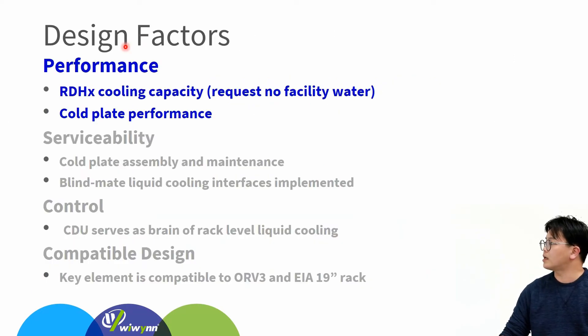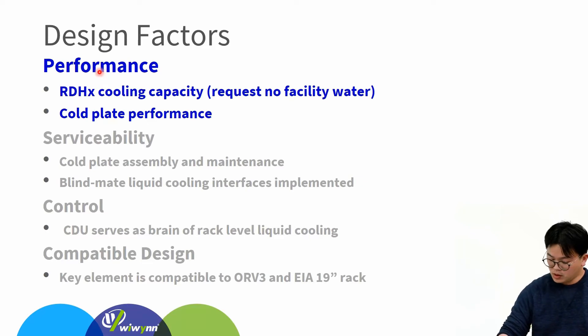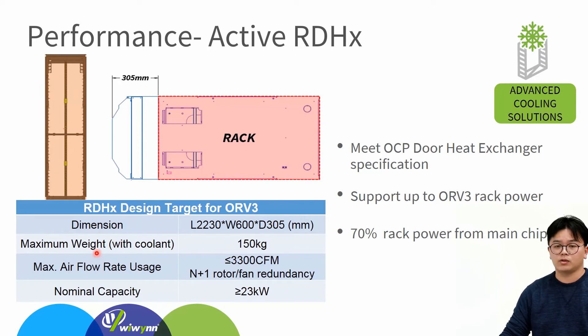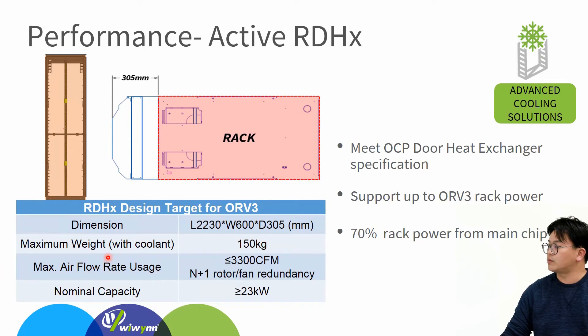I would like to share the design factors and targets we plan to address. First is performance. The cold plate and active rear-door heat exchanger are two key parts in this solution for heat dissipation. The active rear-door heat exchanger mechanical dimensions will follow and meet the OCP heat exchanger spec — you can check the detailed dimensions here. The total weight with coolant will be under 150 kilograms. The current Open Rack V3 power design supports up to 33 or 36 kilowatts per rack, so we must limit maximum airflow usage. To meet the 0.1 CFM per watt design target, airflow usage will be under 3,300 CFM, supporting one fan or one rotor redundancy.